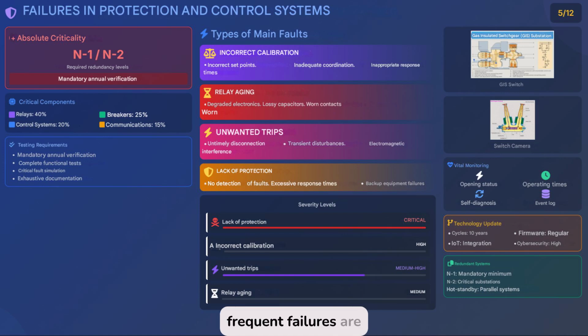Among the most frequent failures are incorrect calibration, which generates unnecessary trips or a lack of response to real faults. Relay aging, which produces silent errors. Unwanted trips due to interference, with a direct impact on service continuity. And a complete lack of protection, the most critical situation, where the system fails to respond and damage worsens.